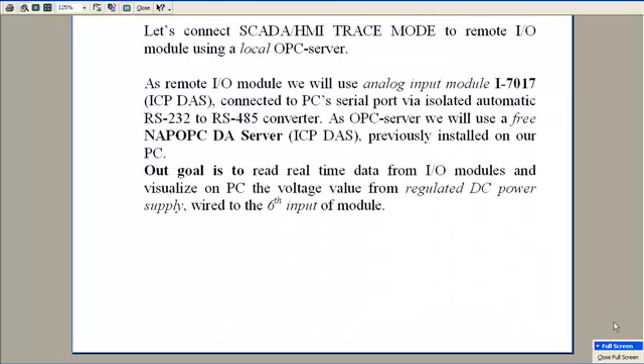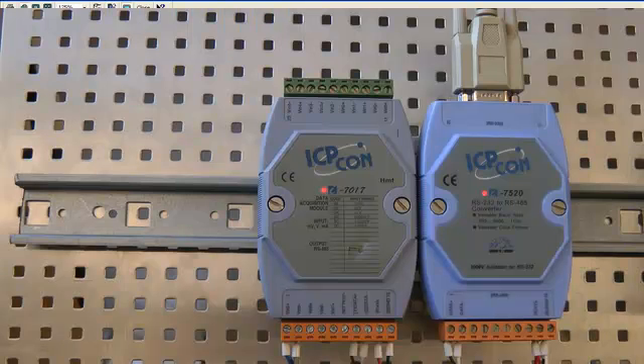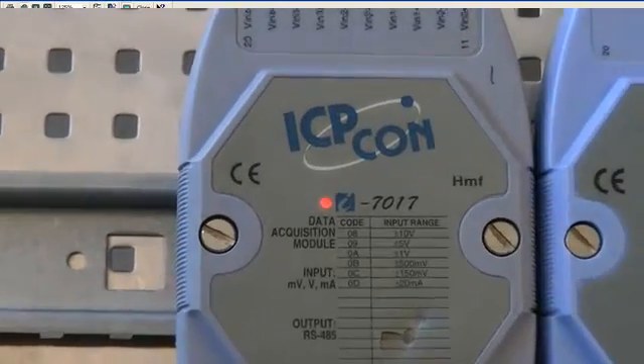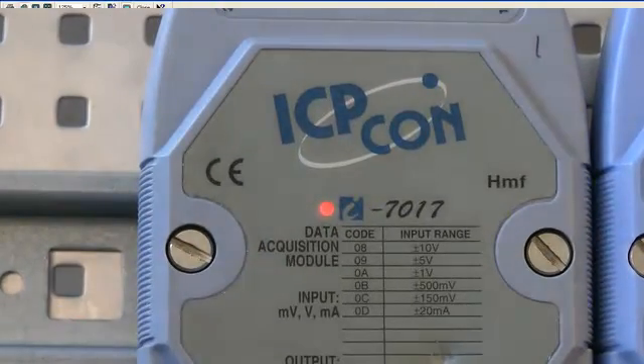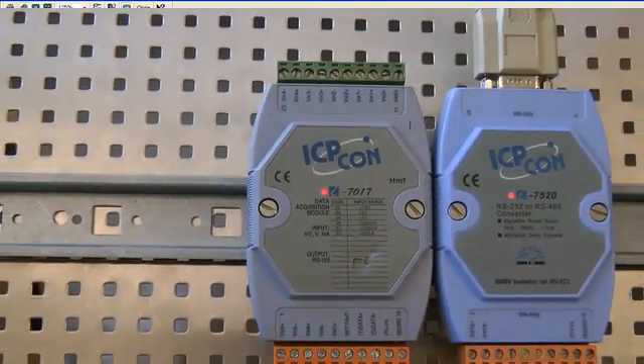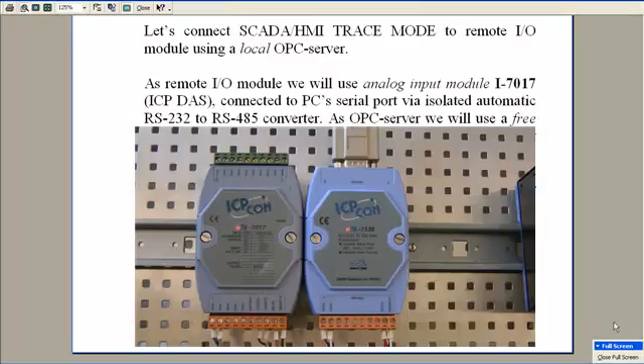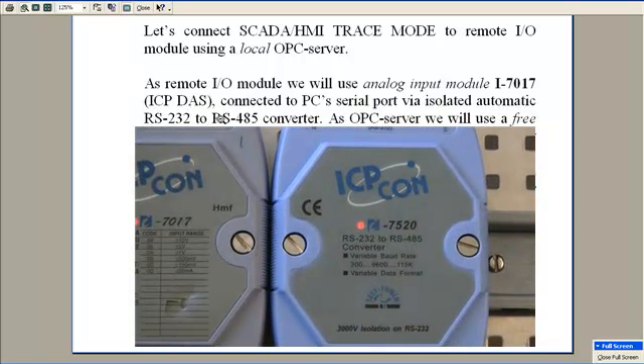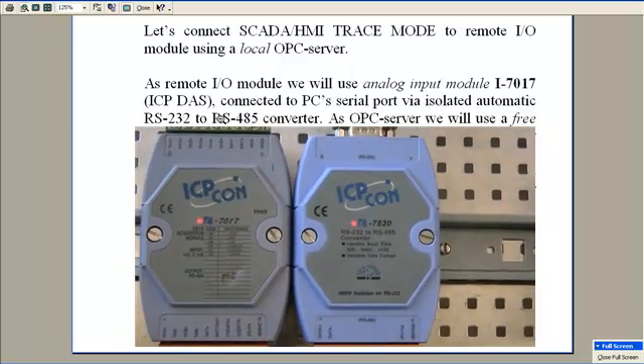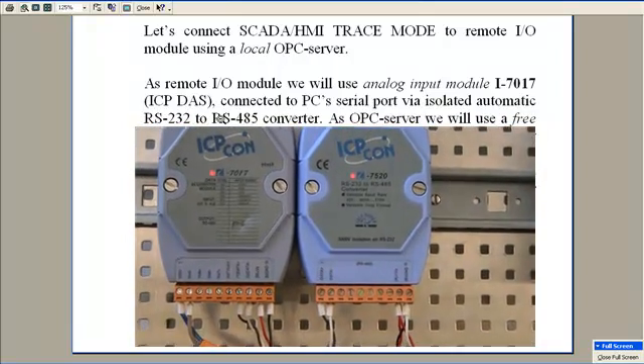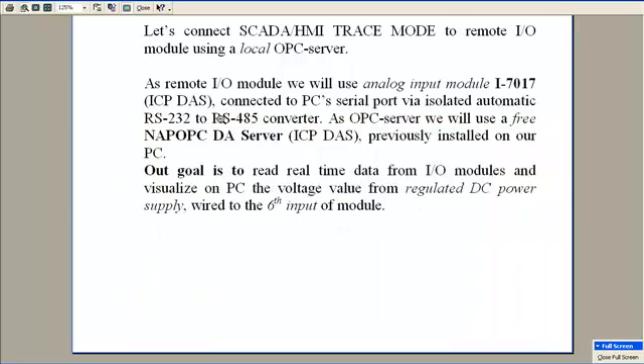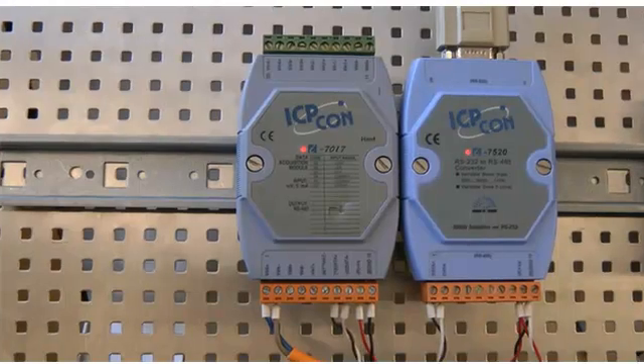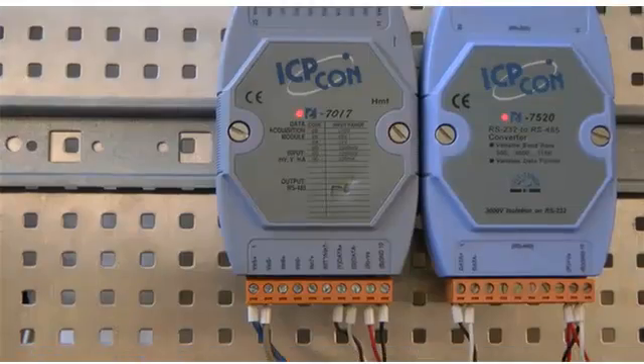As remote I/O we will use analog input module I-7017 connected to PC's serial port via isolated automatic converter. As OPC server we will use a free version of NAP OPC DA server previously installed on our PC. Our task is to read real-time data from I/O module and visualize on PC the voltage from regulated DC power supply wired to the 6th input of the module.